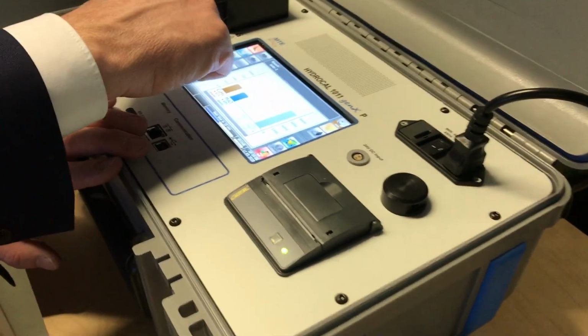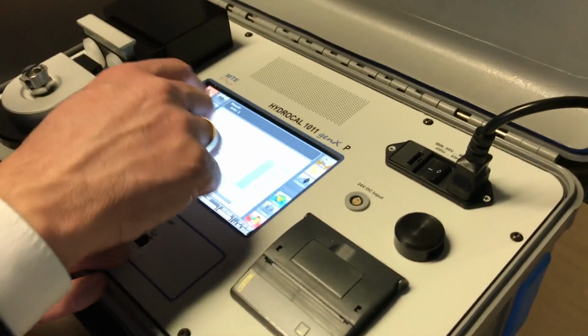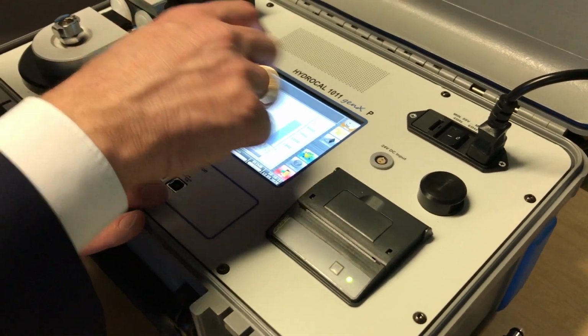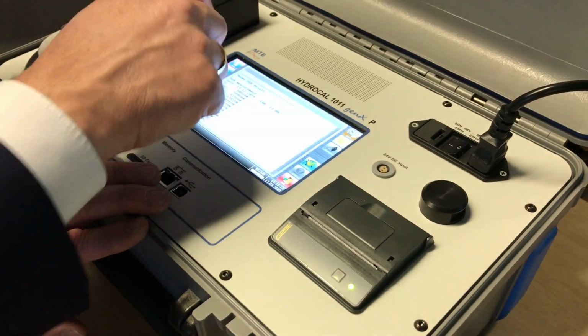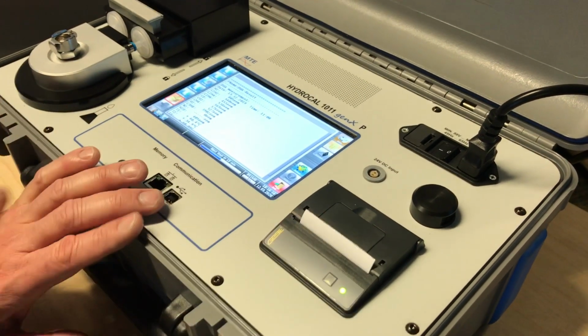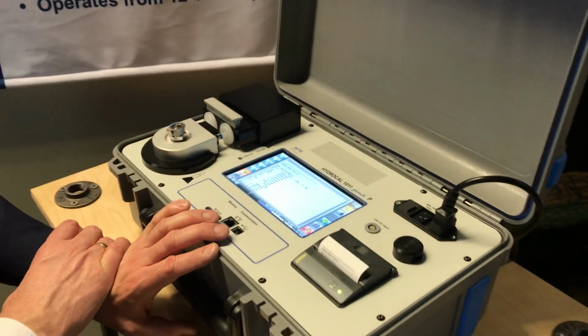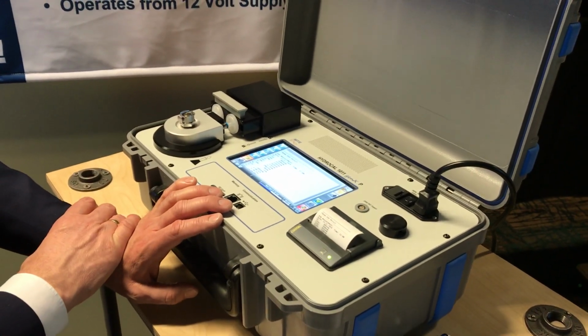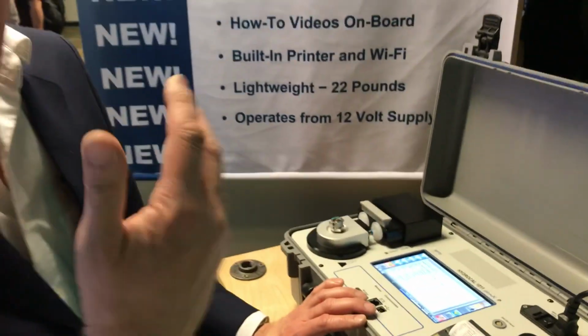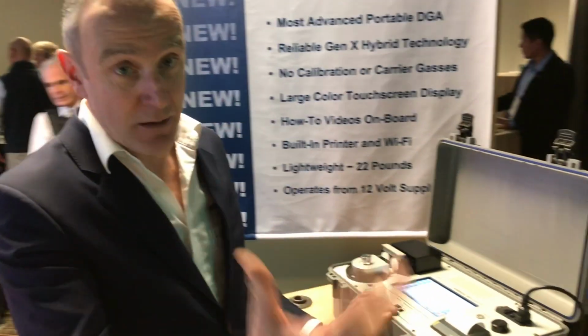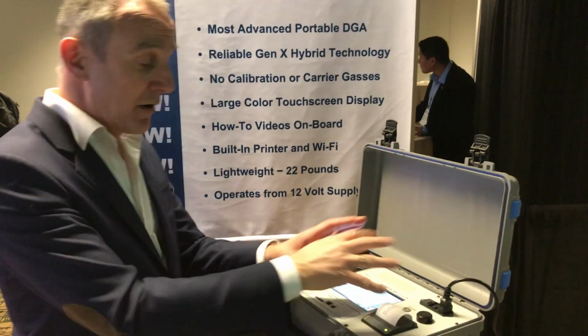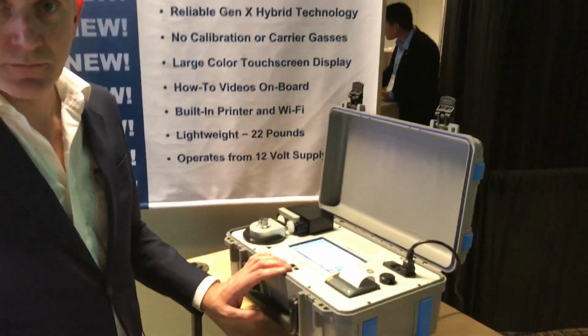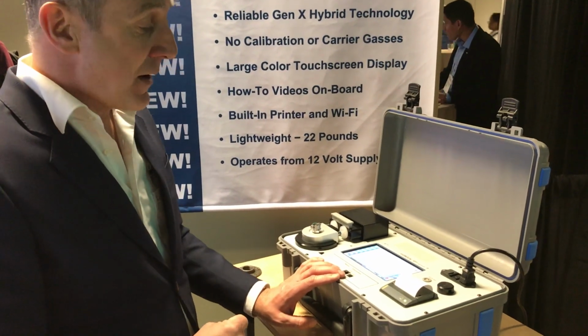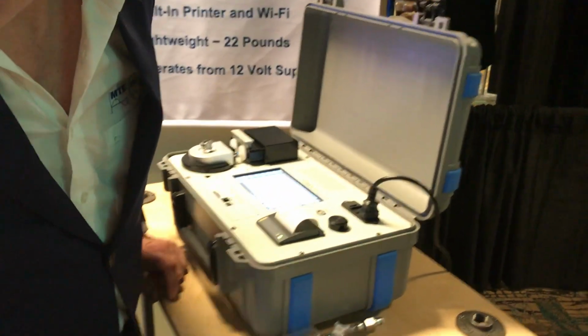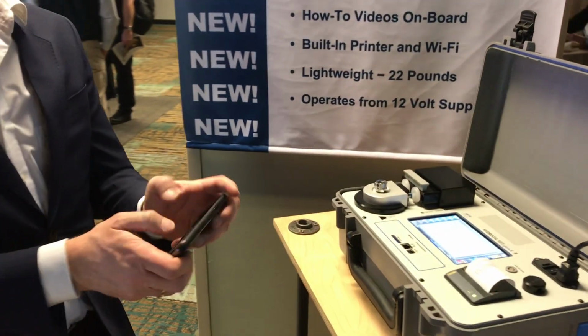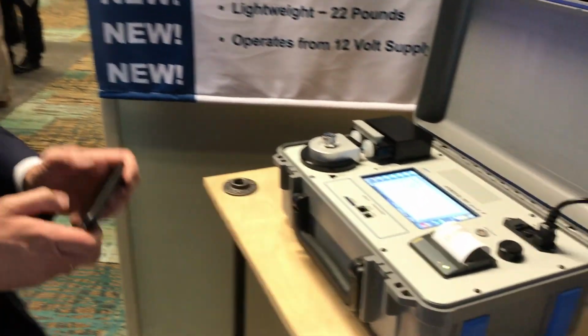If it's required, it's also possible to print the results. So there is a printout with all the different dissolved gases, and of course you can enter the name of the substation, the name of the utility, the model of the transformer, the power of the transformer, so that you have full documentation. Very important as well, there is a Wi-Fi interface, so the device can be operated from any smartphone, notepad or tablet remotely.